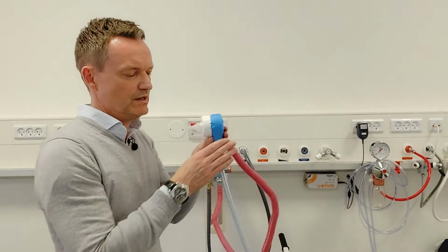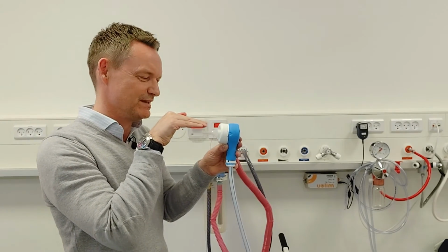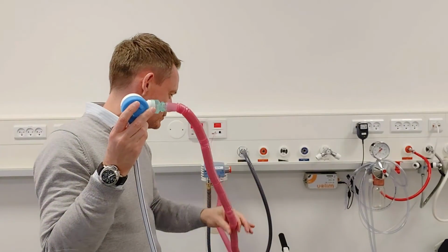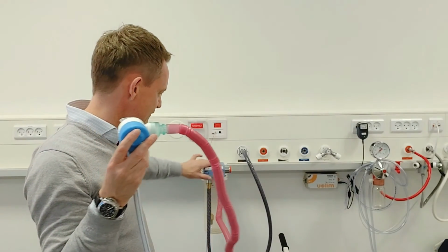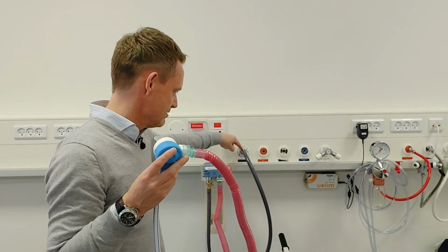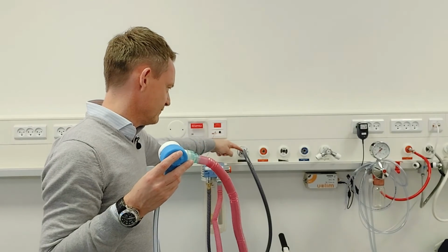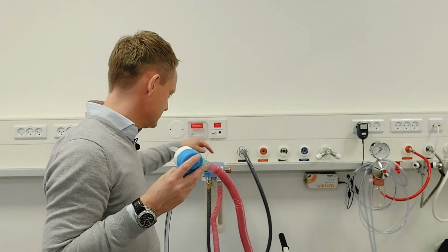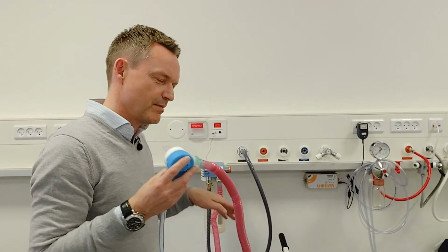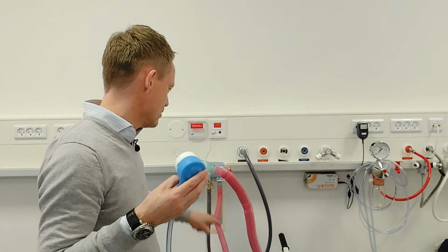So the patient will inhale through the mouthpiece. They will push back on the same mouthpiece with their expiration. That will go into my pink tube, my pink hose, and go over to my buffer. My buffer has holes on the side to protect the patient from a high negative pressure that might come from a vacuum pump, an AGS pump that goes off with too high volume. It will also protect the patient and the system from a high positive pressure that could come from a patient blowing out really heavily. So all my expired gas will then go over to my buffer.